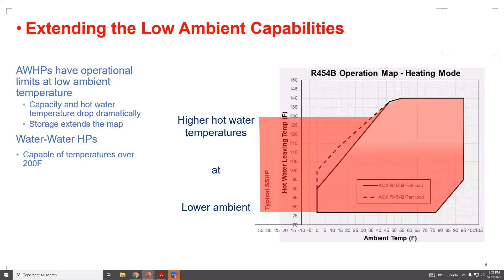So what do we do in this instance? Water-to-water products have the technology to get you up to those elevated water temps you need. As soon as we go below where air source heat pumps are capable of operating, this is when water-to-water heating equipment becomes really viable. As long as we have water and can pull heat out of it, we can operate at any ambient temperature, and we'll be able to make higher temperatures than with air source products.